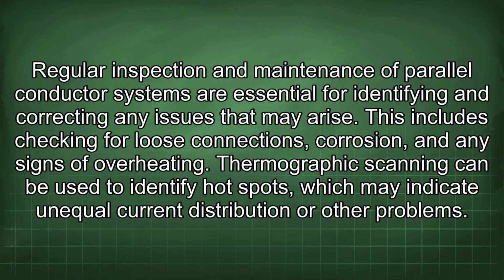Regular inspection and maintenance of parallel conductor systems are essential for identifying and correcting any issues that may arise. This includes checking for loose connections, corrosion, and any signs of overheating. Thermographic scanning can be used to identify hotspots, which may indicate unequal current distribution or other problems.